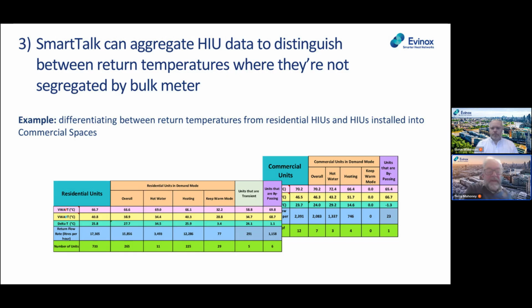By aggregating the return temperatures based on HIU data, we could separate the residential HIUs from the commercial spaces, so we could see whether the commercial HIUs were performing better or differently than the residential ones, and vice versa. In this example, there were different responsibilities for the commercial units than the residential.